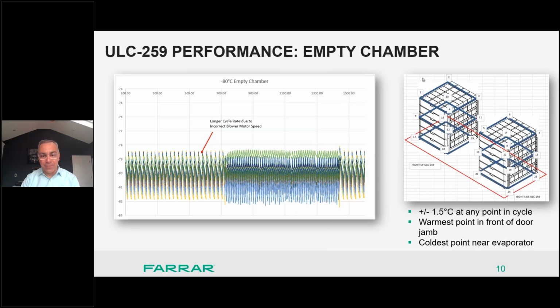So the takeaway here is we're really maintaining a really tight temperature tolerance across the freezer, with the warmest point along the door gasket, the largest heat infiltration area in the freezer, and the coldest point near the evap motor and blower at the top of our ductwork. So let's take a look at how the performance looked when you ghost load it.